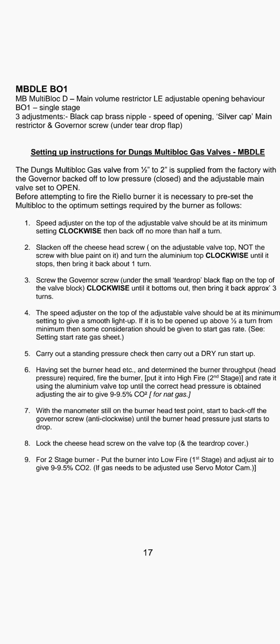Step four: the speed adjuster on top of the adjustable valve should be at its minimum setting to give a smooth light-up. If it is to be opened up above half a turn from minimum, then some consideration should be given to start gas rate — see setting start rate gas sheet.